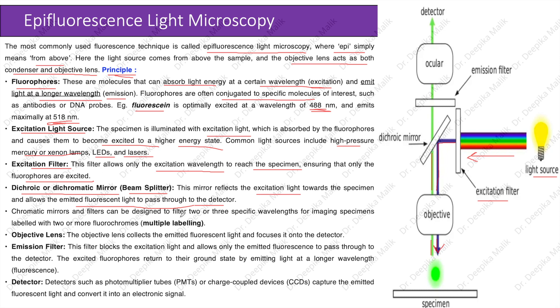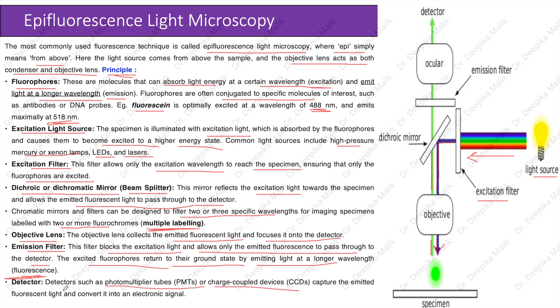Chromatic mirrors and excitation filters can be designed to filter two or three specific wavelengths for imaging specimens labeled with two or more fluorochromes — this is known as multiple labeling. The objective lens collects the emitted fluorescent light and focuses it onto the detector. The emission filter blocks the excitation light and allows only the emitted fluorescence to pass through to the detector.